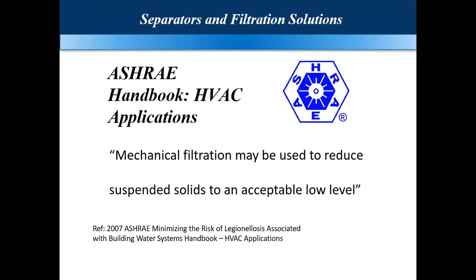So the ASHRAE handbook suggests that mechanical filtration may be used to reduce suspended solids to an acceptable low level. Also, the ASHRAE Green Guide from 2010 says continued filtration of the circulating water and a basin sweeping system should be considered to keep the basin free from visible dirt, which is generally 40 micron or larger.